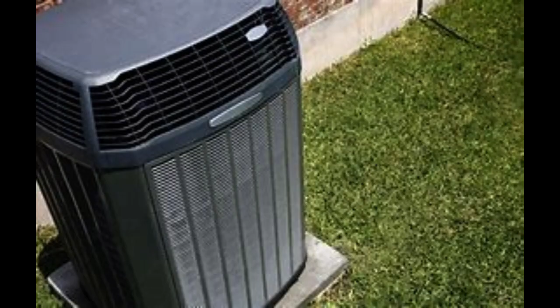B. Report as deficient: (i) Inoperative units. (ii) Deficiencies in the thermostats. (iii) Inappropriate location. (iv) The lack of protection from physical damage. (v) Burners, burner ignition devices or heating elements, switches, and thermostats that are not a minimum of 18 inches above the lowest garage floor elevation, unless the unit is listed for garage floor installation.